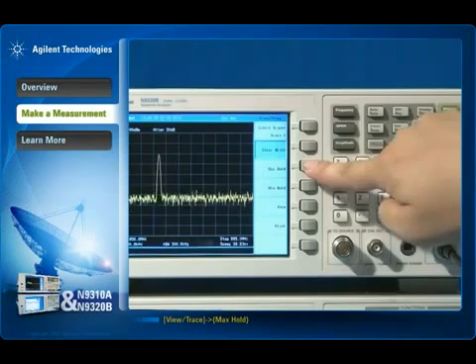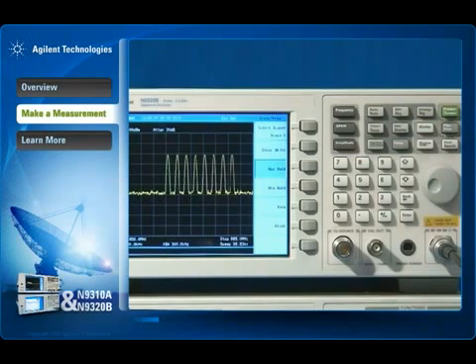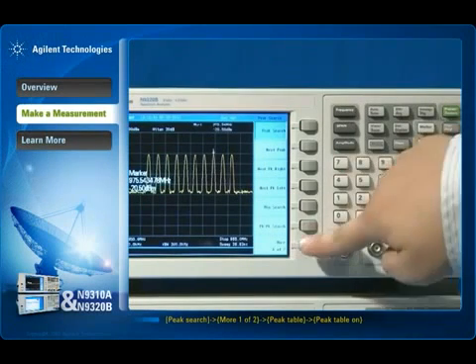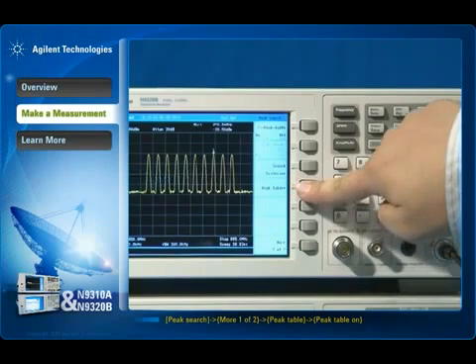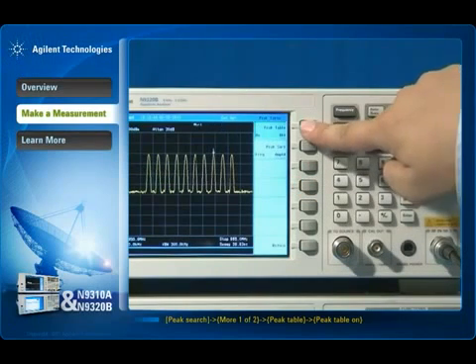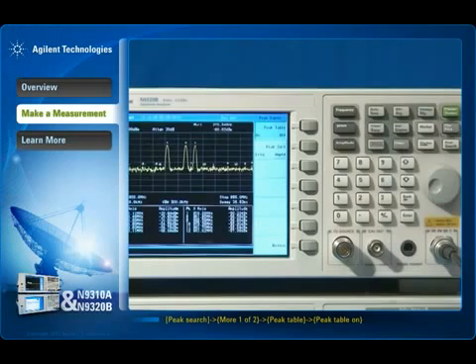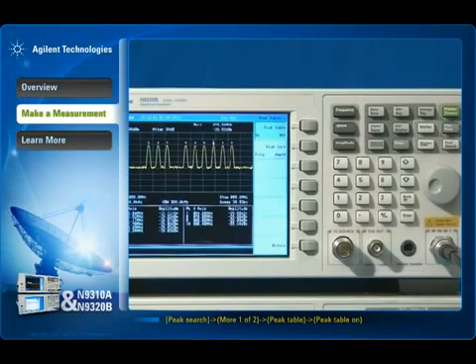Use the max hold to keep the sweep signals on the screen and the peak table function to list the peak signals across the bandwidth. These are typical operations to catch transient signals.